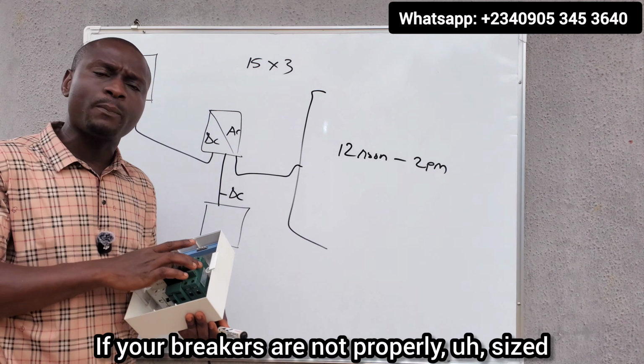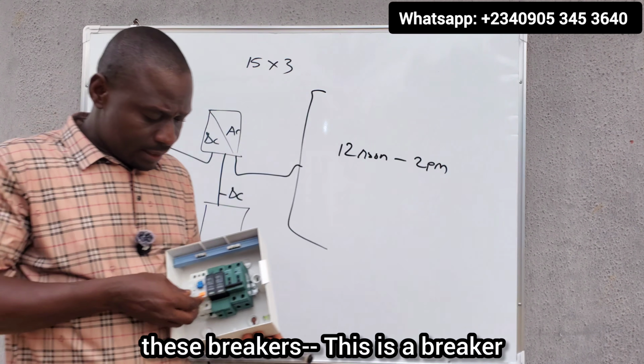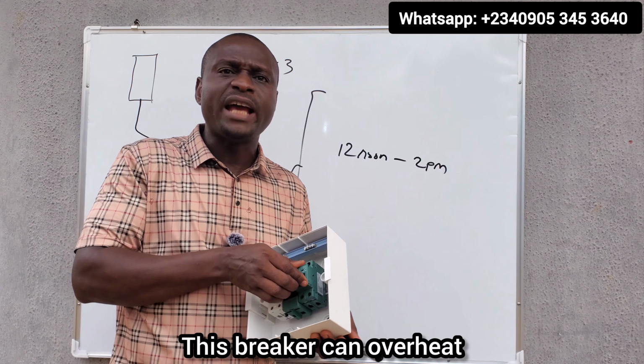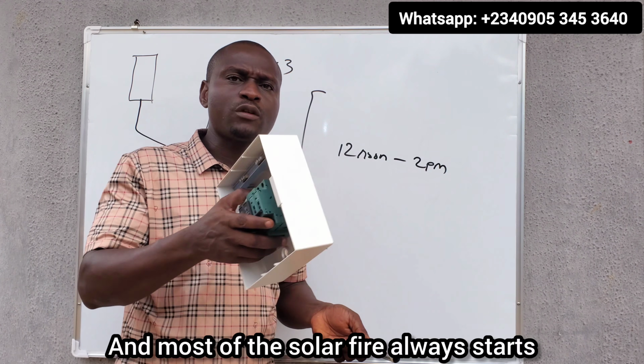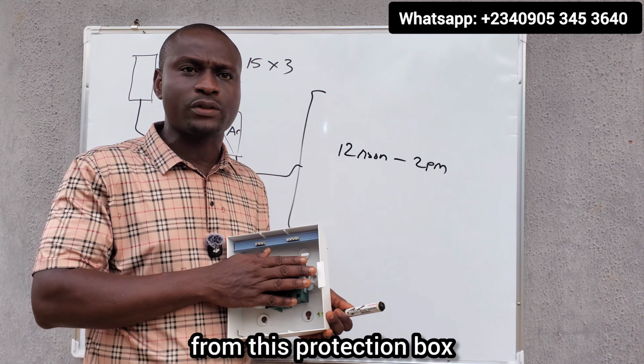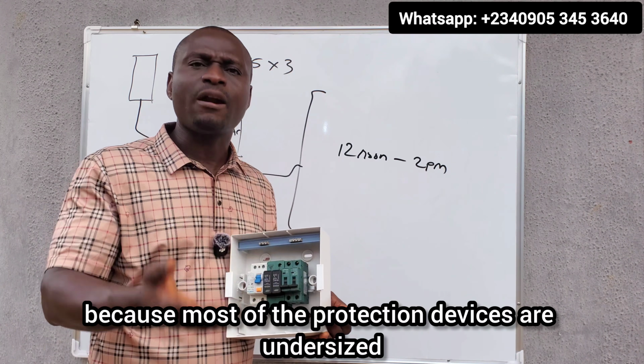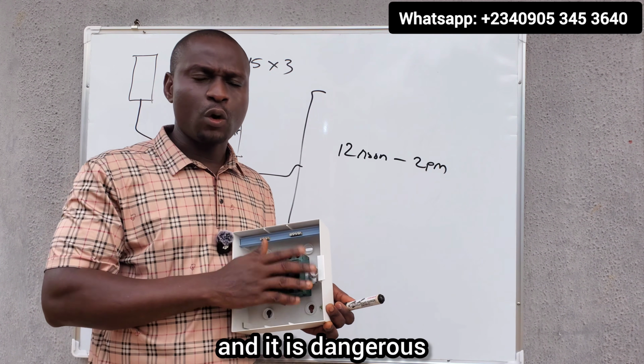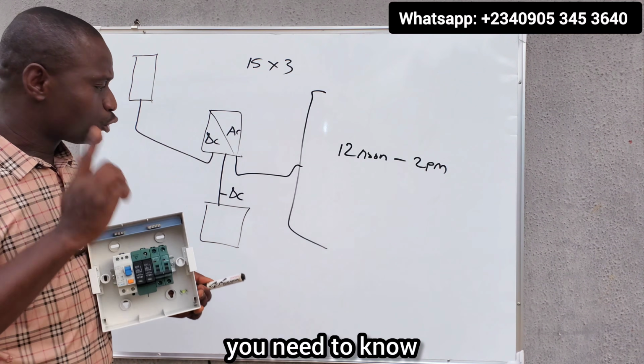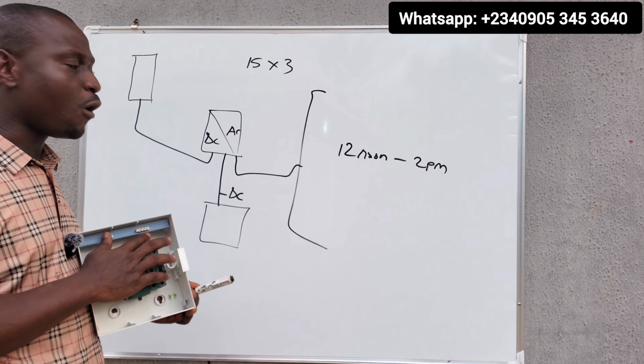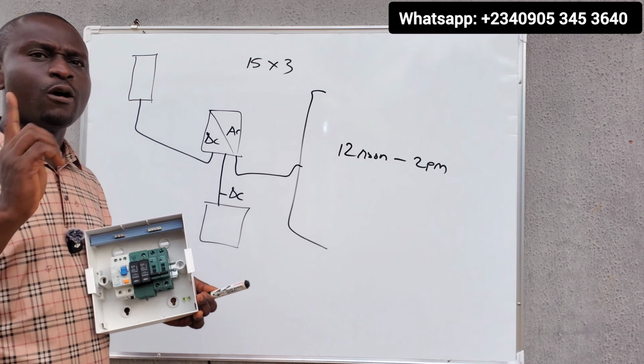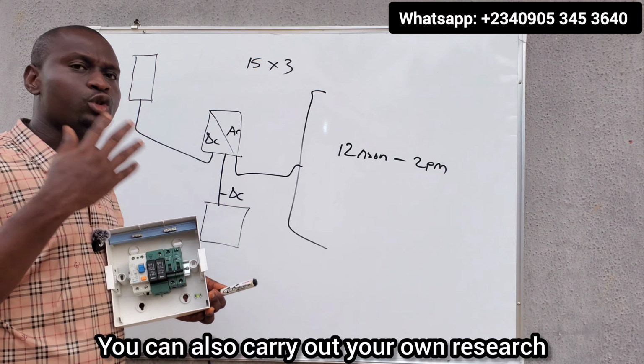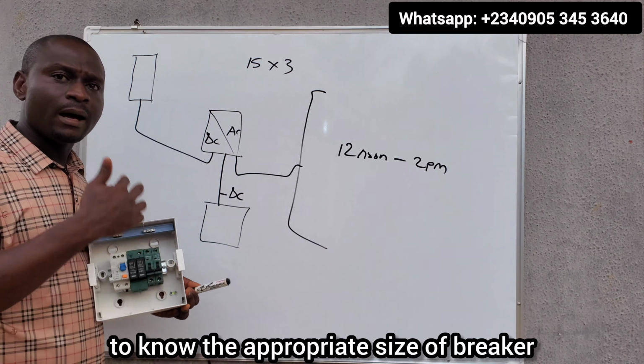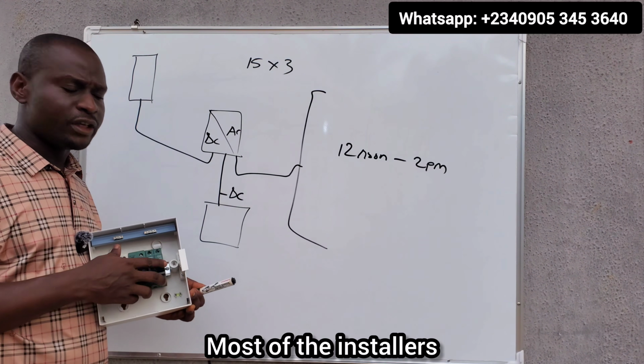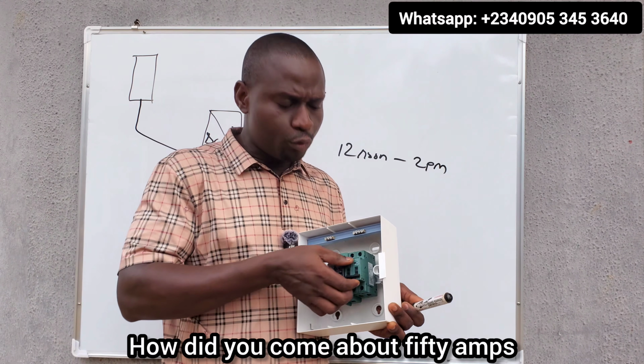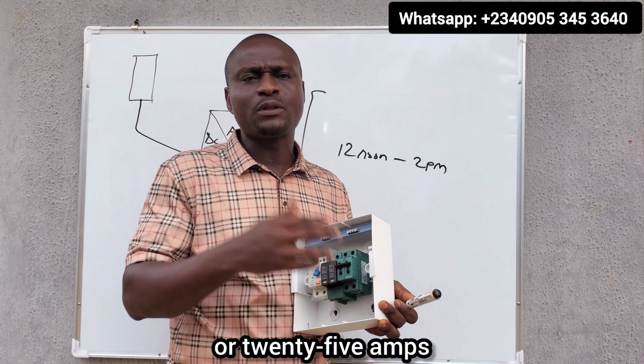Now, the current that the solar panels will be generating will also be high. If your breakers are not properly sized, this is a breaker. This breaker can overheat. It can cause a fire. And most solar fires start from this protection box because most of the protection devices are undersized and it is dangerous. So as a system designer, you need to know how to properly size these overcurrent protection devices. Also, as a homeowner, you can carry out your own research to know the appropriate size of breaker and the appropriate size of fuse to use. Most of the installers, you can engage them, you can ask them, how did you come about 50 amps or 25 amps or 30 amps?